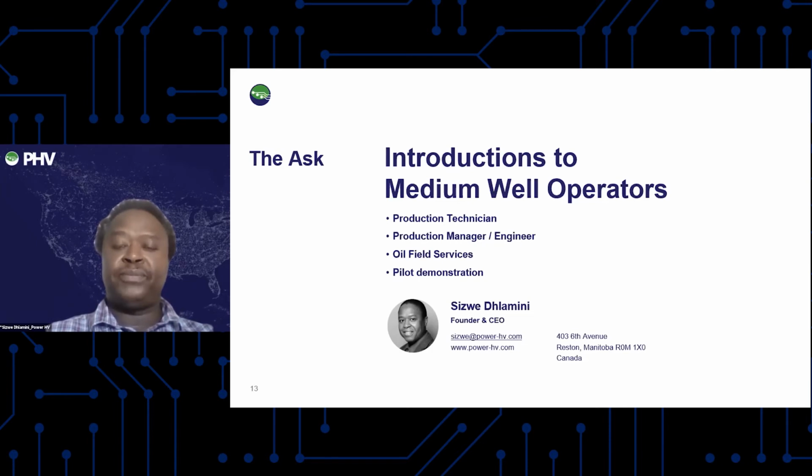Thank you. Another follow-up question from Vincent. Where are your sensors built? Where is your IP? And what is the sensing technology? We build our own sensors. We have our own proprietary sensor specifically developed for partial discharge detection. We add methane detection sensors, vibration sensors, audio, and other sensors, so that when we detect a methane leak, we have multiple sources of inputs that allow us to know that this is definitely a leak and not a false alarm. And our intellectual property, we have one patent, which is for bushings, and we are filing some patents for sensors. So those are ongoing and in progress.